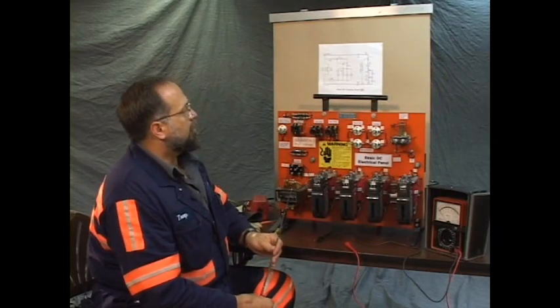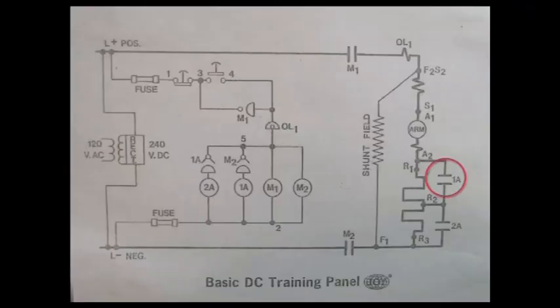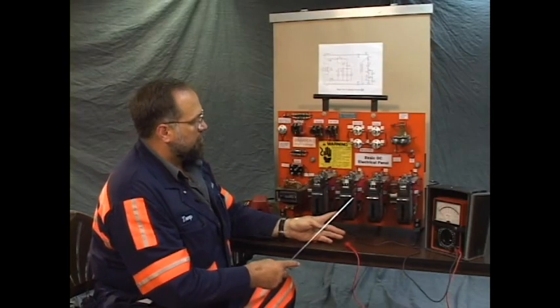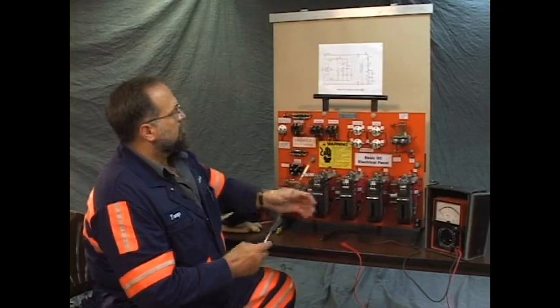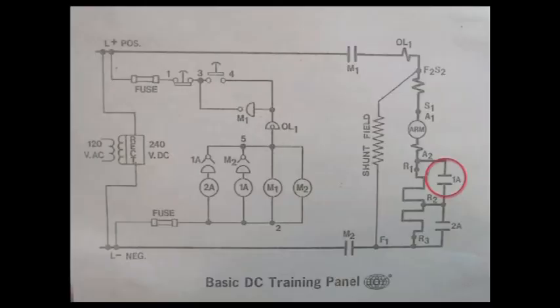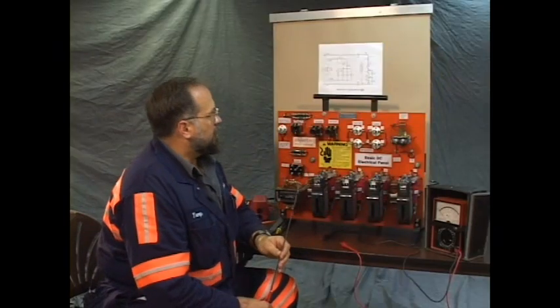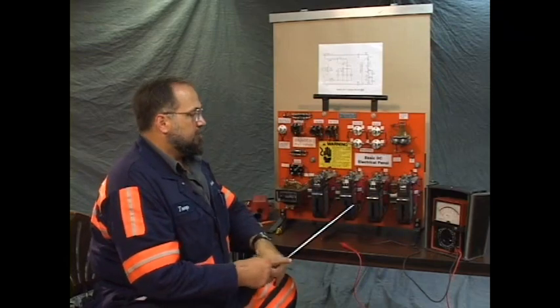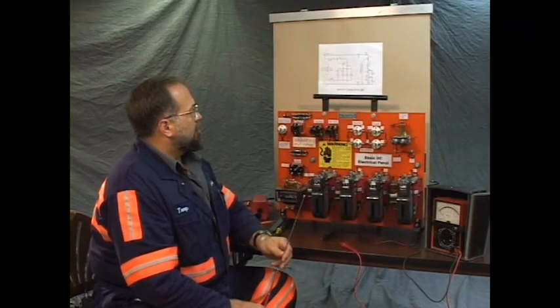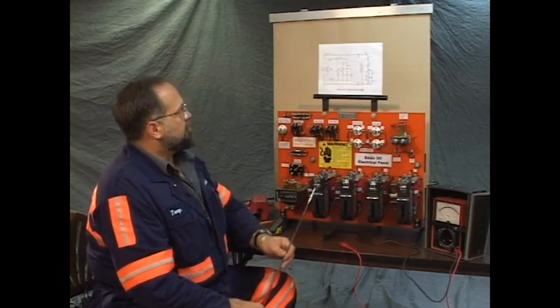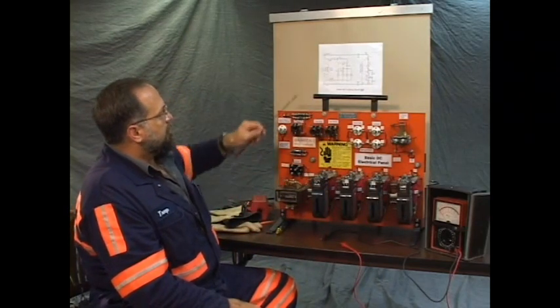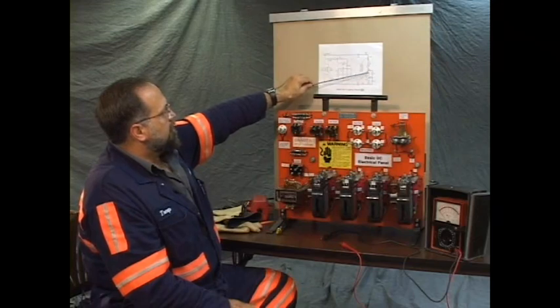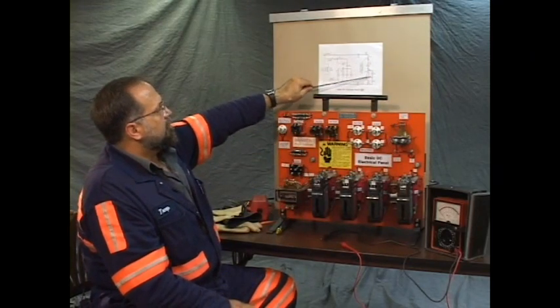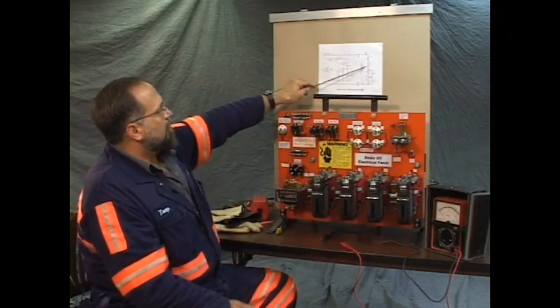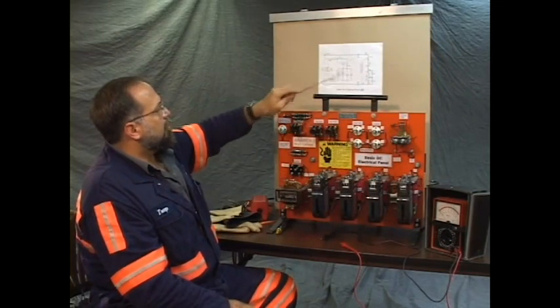Now, we can take part of the resistor away by closing the 1A contactor. That's this one here. When this contactor closes, as with the drawing, it shunts this resistance. It gives it a path around it instead of through it. Electricity will take the path of least resistance. The contactor poses a much smaller opposition to the flow of current than this resistor, so it would choose that path. And the resistor drops voltage, while with the path around it, you would have no voltage drop. And the motor would see more voltage, and the light would become brighter.